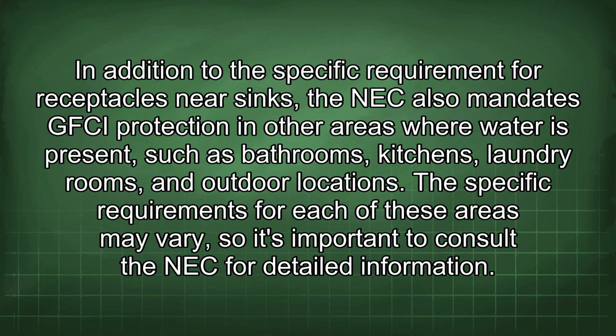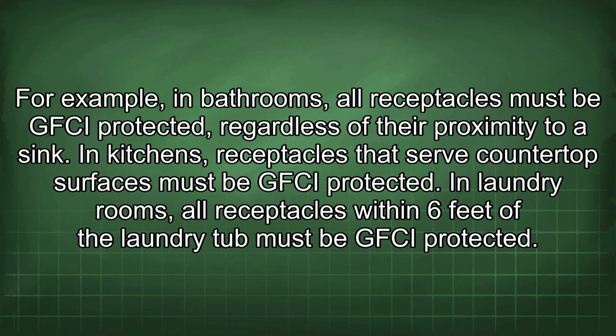In addition to the specific requirement for receptacles near sinks, the NEC also mandates GFCI protection in other areas where water is present, such as bathrooms, kitchens, laundry rooms, and outdoor locations. The specific requirements for each of these areas may vary, so it's important to consult the NEC for detailed information. For example, in bathrooms, all receptacles must be GFCI protected, regardless of their proximity to a sink. In kitchens, receptacles that serve countertop surfaces must be GFCI protected. In laundry rooms, all receptacles within 6 feet of the laundry tub must be GFCI protected.